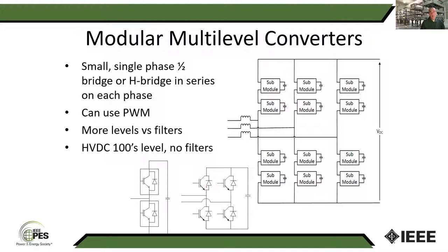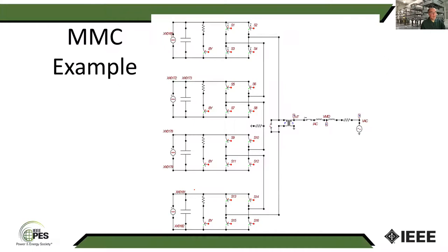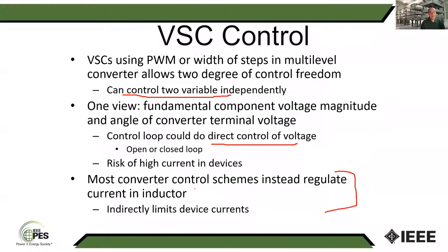I know that one of the applications for shipboard systems, they actually size their generators to be able to supply a bolted three-phase fault at the terminals for up to a second. These do not have the ability to have that kind of overcurrent. In most cases, the people that design these converters size them so they can do about 120% of rated current indefinitely, but they can't go much above that. And so by doing this, it limits the device currents.